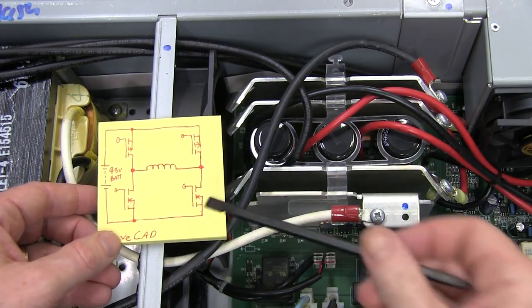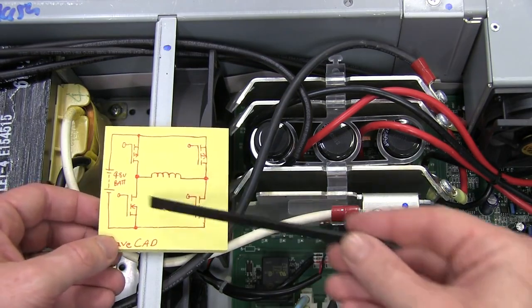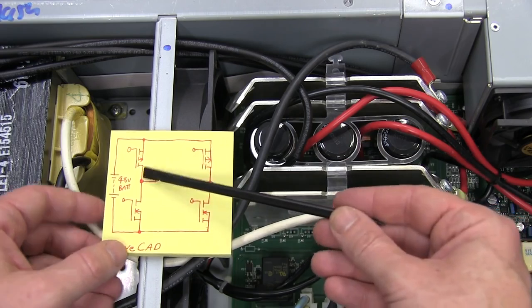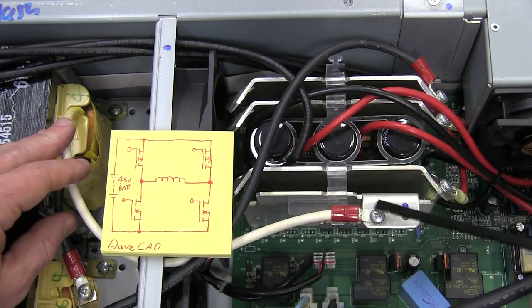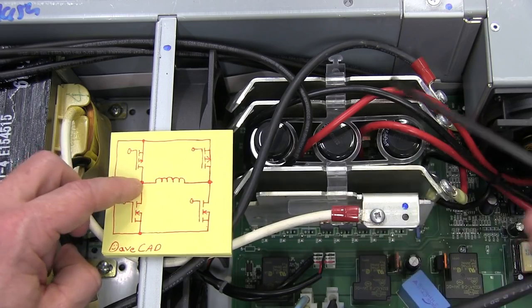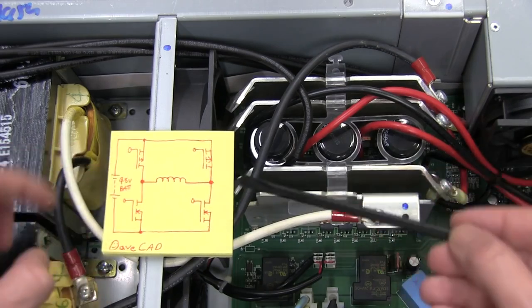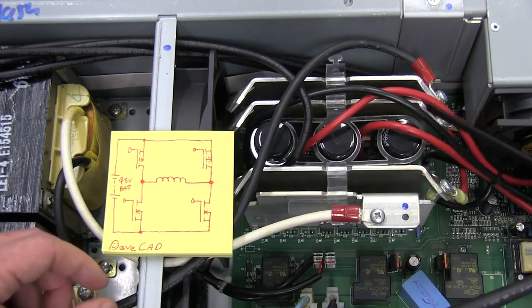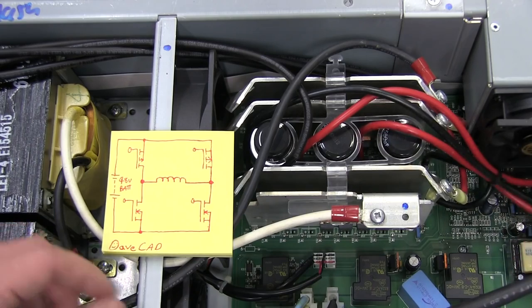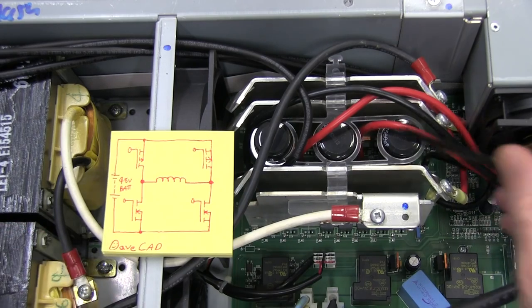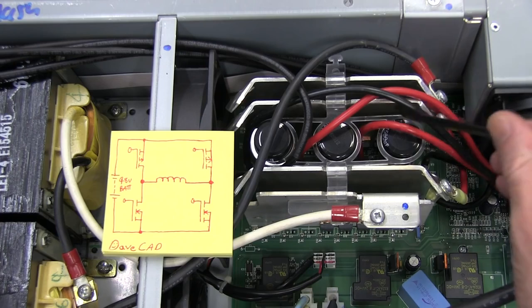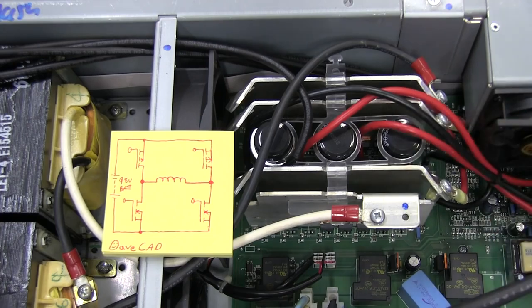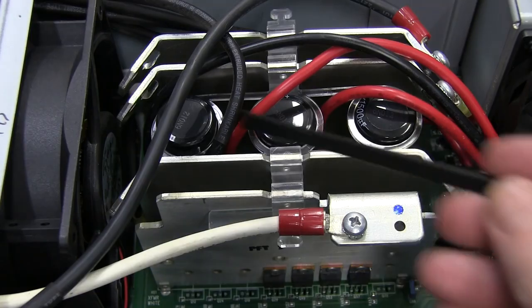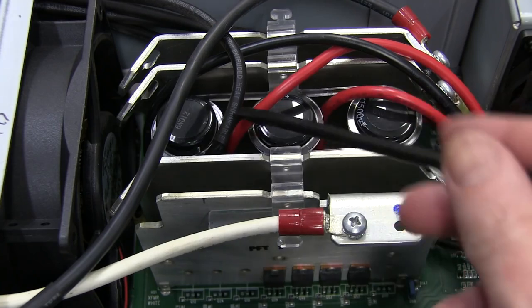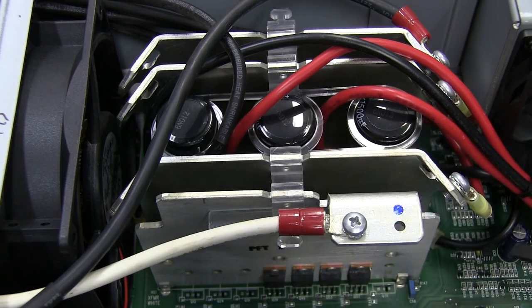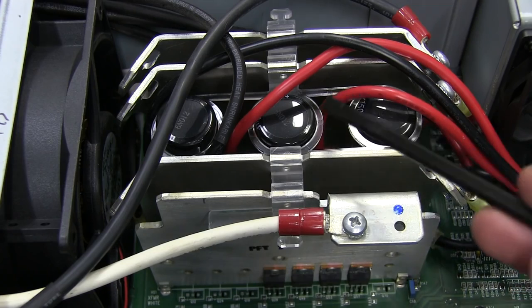But you can clearly see that's the configuration we've got. We've got our transformer hooked onto 2 of the taps effectively on that H bridge, the center taps there, and then we've got our battery hooked onto these other 2 down here. If we follow the wires, we'll find that these 2 plates here go down to the battery pack. I find it rather interesting that they've got quite a hefty amount of capacitance there across the battery terminals.